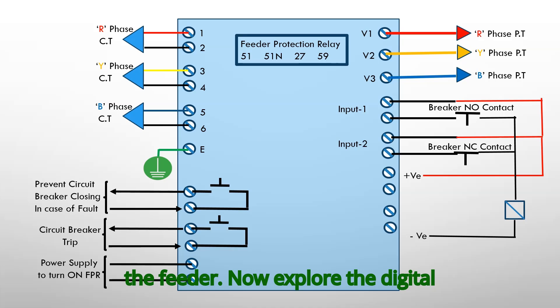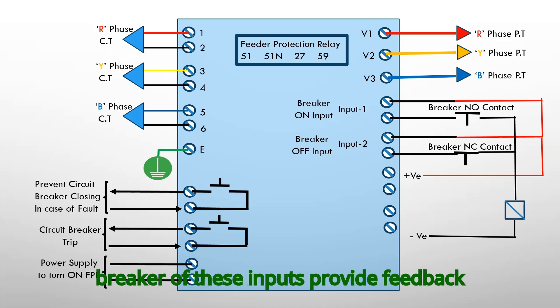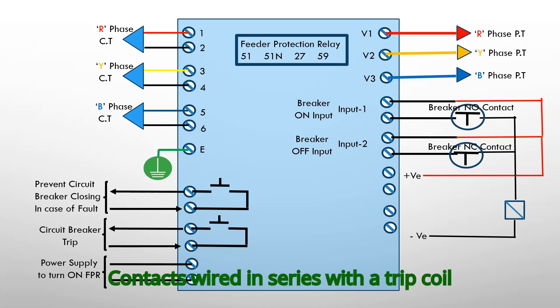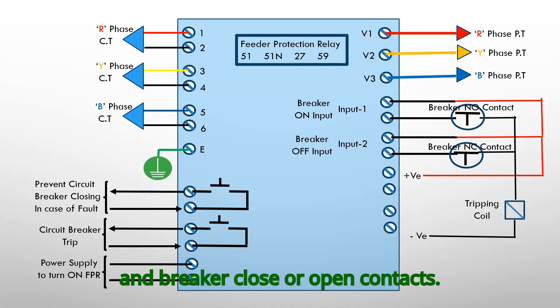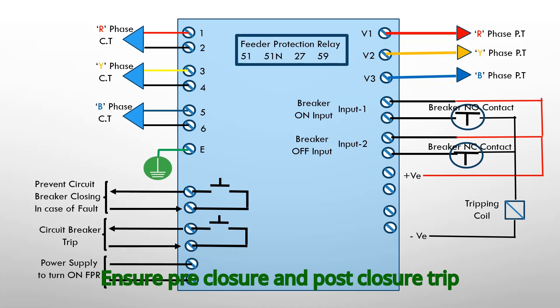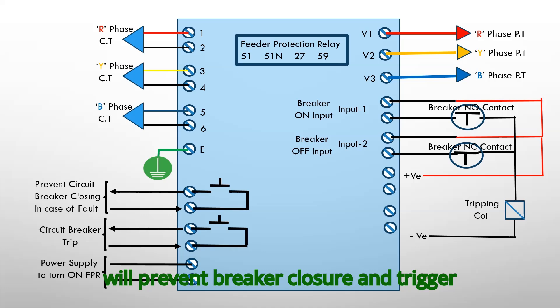Now we will explore the digital inputs to the relay. We have configured two critical inputs: breaker on and breaker off. These inputs provide feedback to the relay, confirming the breaker status. Contacts are wired in series with a trip coil and breaker close or open contacts, ensuring pre-closure and post-closure trip circuit supervision. If the relay does not receive these inputs, it assumes trip coil failure, prevents breaker closure and triggers an alarm.